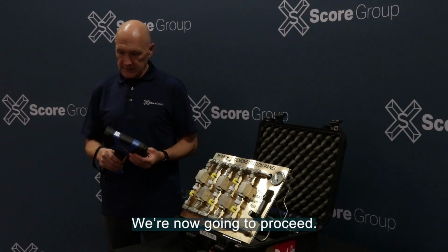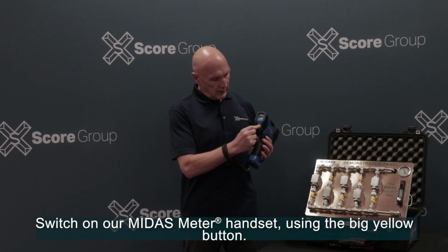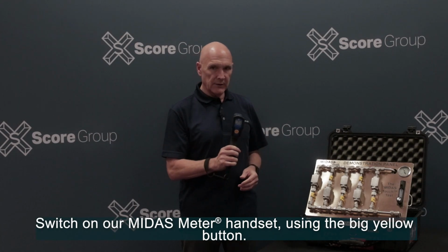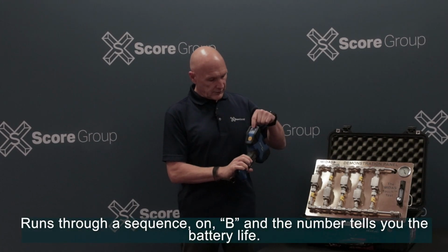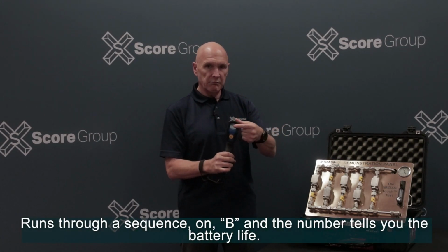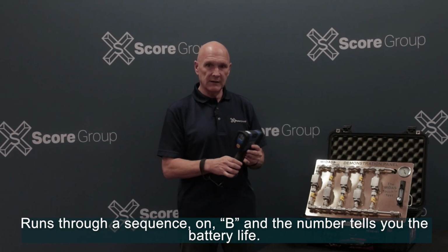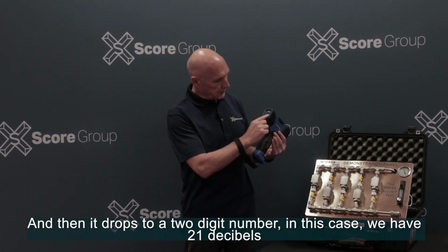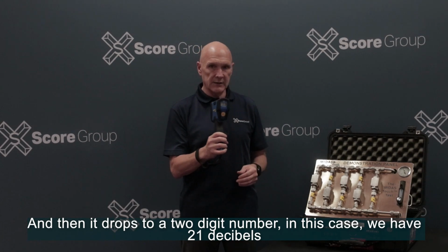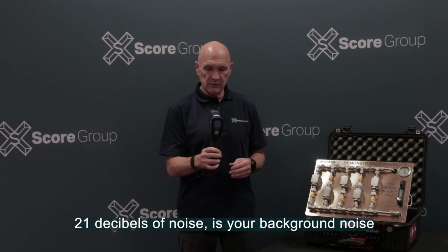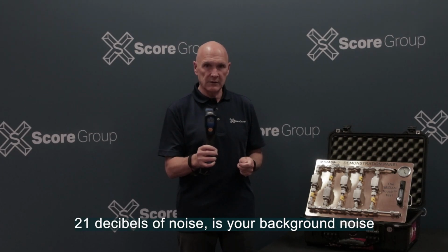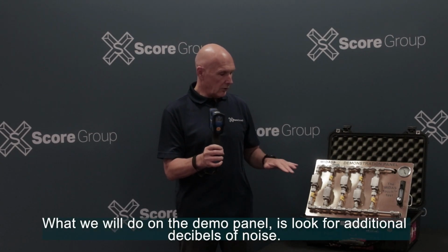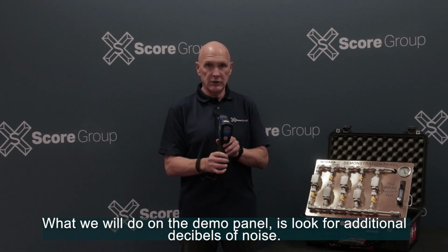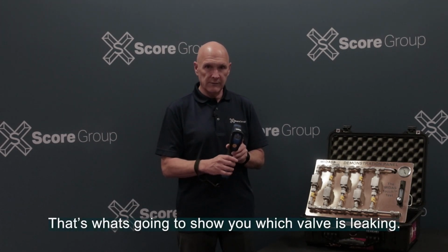We're now going to proceed, switch on our MIDAS meter handset using the big yellow button. It runs through a sequence, on, B and a number tells you the battery life, and then it drops to a 2-digit number. In this case, we have 21 decibels. 21 decibels of noise is your background noise. What we will do on the demo panel is look for additional decibels of noise. That's what's going to show you which valve is leaking.